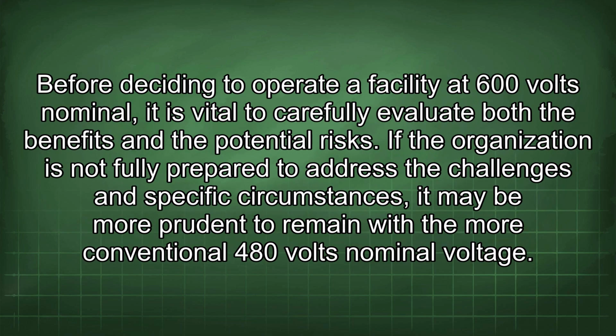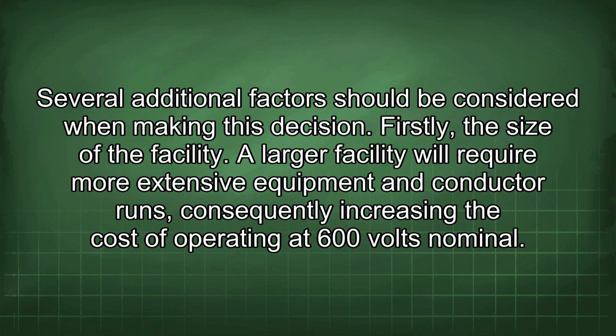Before deciding to operate a facility at 600 volts nominal, it is vital to carefully evaluate both the benefits and the potential risks. If the organization is not fully prepared to address the challenges and specific circumstances, it may be more prudent to remain with the more conventional 480 volts nominal voltage. Several additional factors should be considered when making this decision. Firstly, the size of the facility.